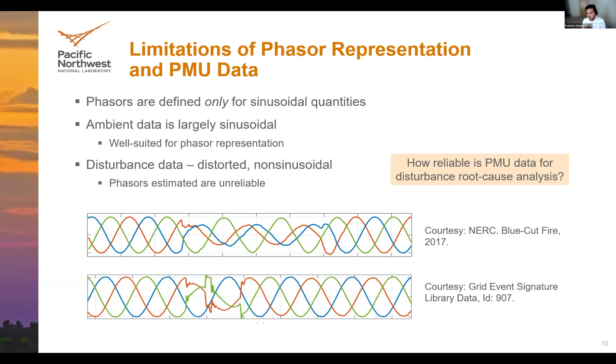Other than the disturbance events I talked about, there are also instances where PMU data might not be a good representation, particularly when monitoring high frequency transients. The PMU data, because of its inherent reporting limitations, which may be 30 or 60 frames per second, can only report frequencies up to its Nyquist reporting rate.